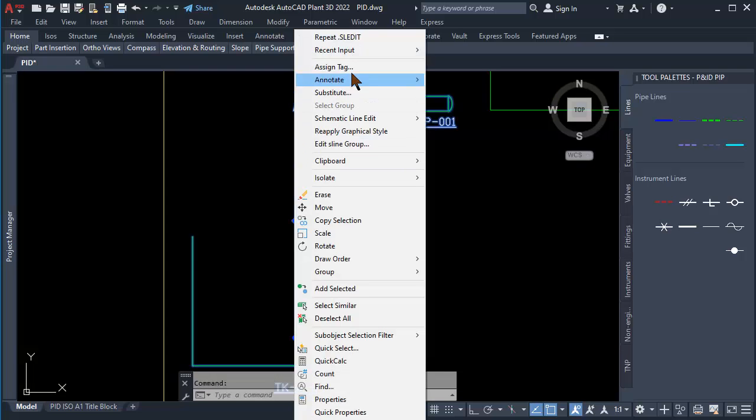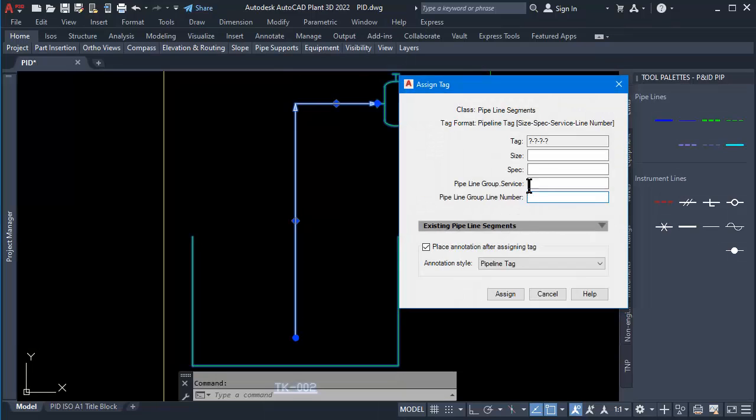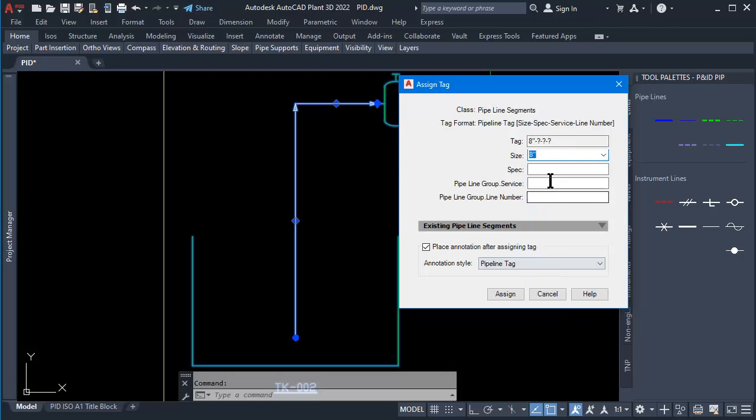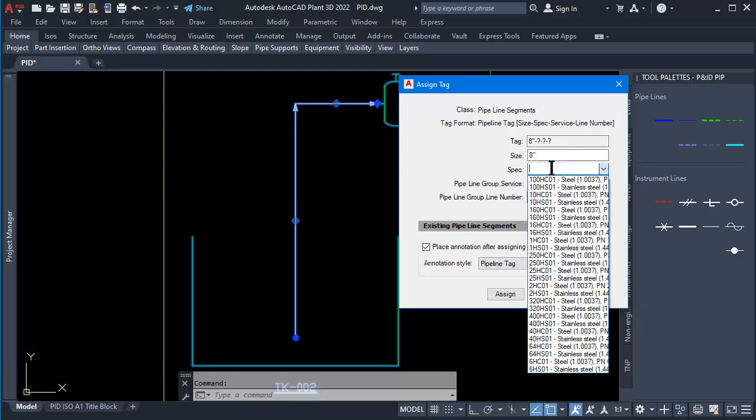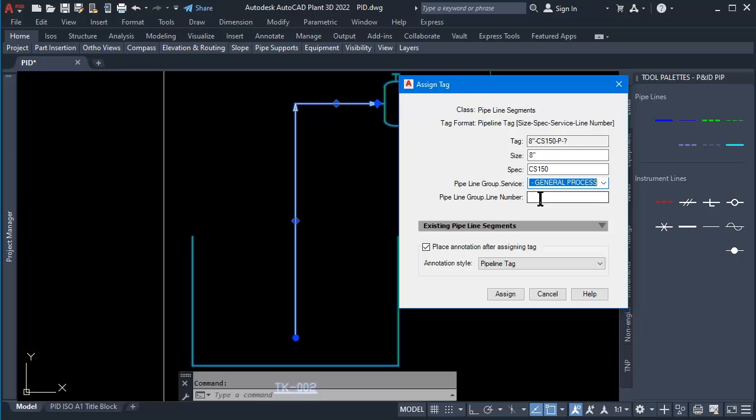Right-click on the process line. Go to Click Assign Tag. Click to select Size Pipe 8 inches. At Spec, type CS 150 pounds. At Service, type P. At Line Number, type 001. Click Assign button then click to place Pipeline Tag.